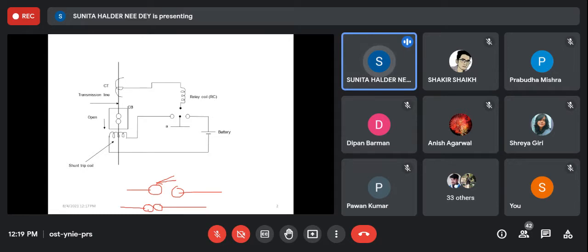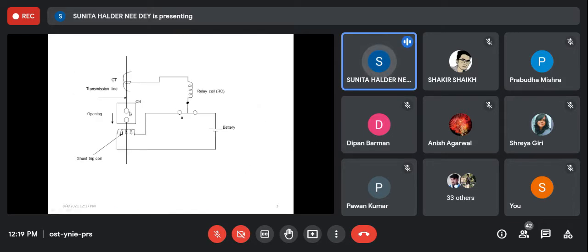Otherwise, what will happen? A contact gap will arise, creating contact resistance. That will be in series with the transmission line, so it will create an unnecessary voltage drop and unnecessary problems. That's why there should be a spring, so that the moving contact or fixed contact is kept at the proper, desired position. That's why they are operated using a motor, and there is a spring mechanism to maintain the moving contact at a particular position.